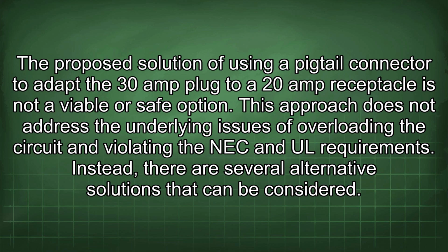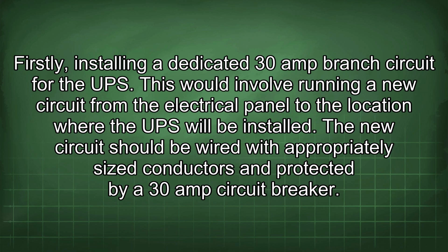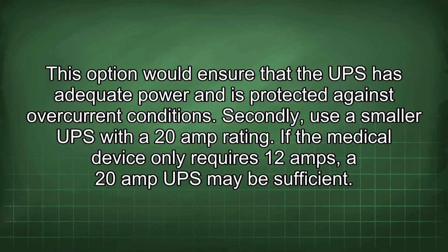This approach does not address the underlying issues of overloading the circuit and violating the NEC and UL requirements. Instead, there are several alternative solutions that can be considered. Firstly, installing a dedicated 30 amp branch circuit for the UPS. This would involve running a new circuit from the electrical panel to the location where the UPS will be installed. The new circuit should be wired with appropriately sized conductors and protected by a 30 amp circuit breaker. This option would ensure that the UPS has adequate power and is protected against overcurrent conditions.